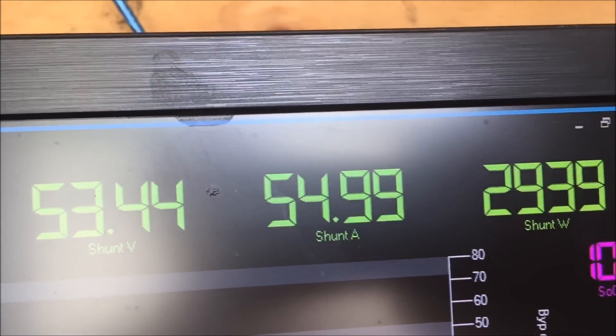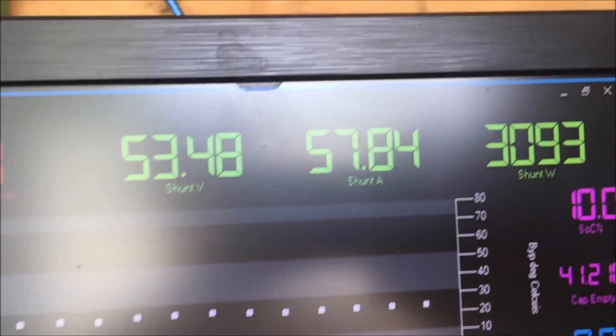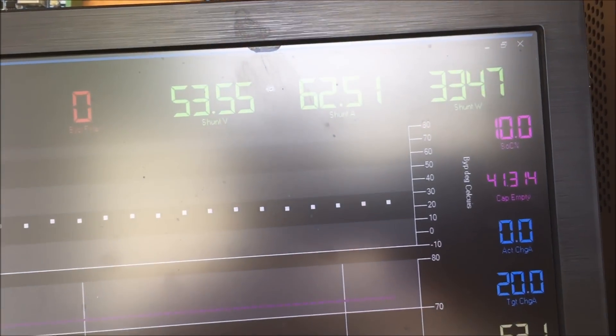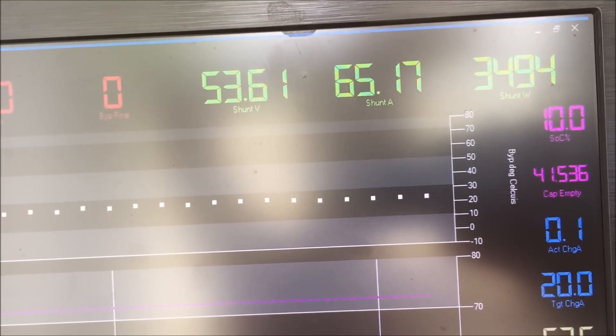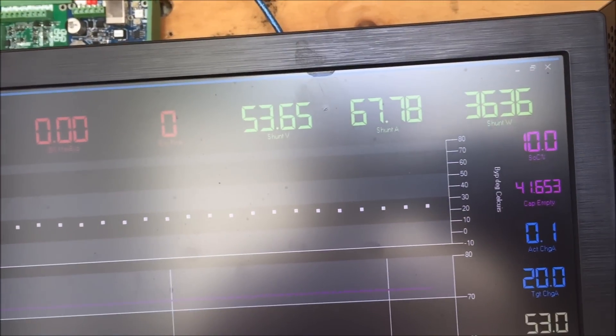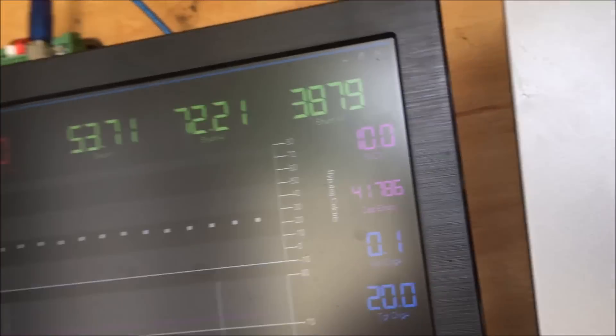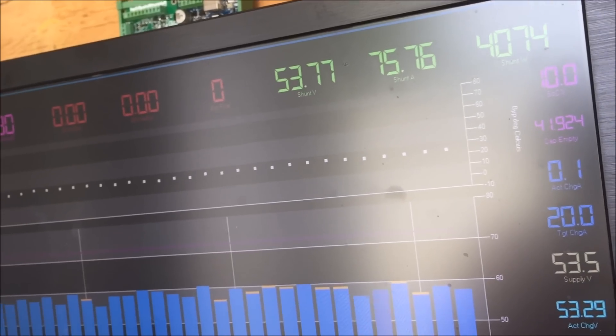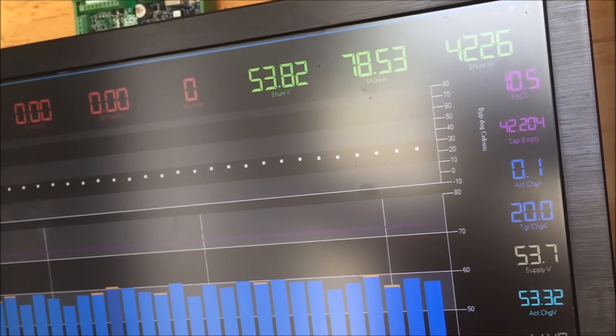It's running and now it's slowly ramping back up — it doesn't just jump up, it slowly ramps up. There we go, that's 60 — that one just clicked and turned on. The watchmon will allow that to turn on in a minute — shaky 70 amps coming back up. Once we get back up to 120 amps we'll have a look at those terminals to see if they're still up in temperature or down.